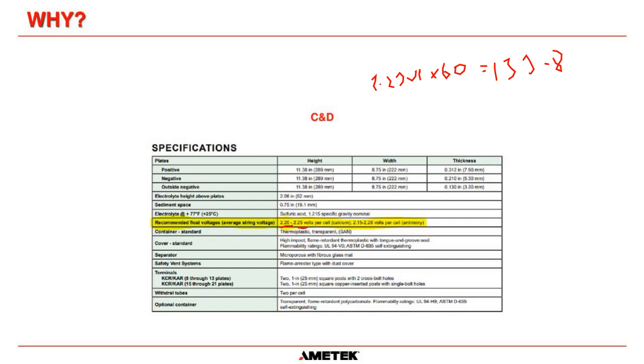Okay, if all of your cell voltages are between 2.2 and 2.25, you do not need to do an equalize, ever, except for when you're going to do a capacity test, because the battery manufacturer says you need to do an equalize before the capacity test.